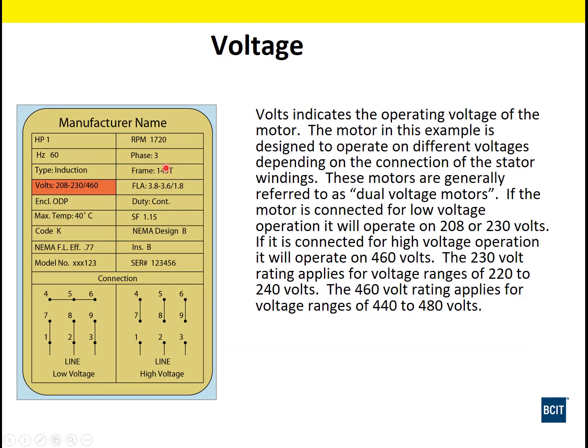Now we look at voltage. It's pretty straightforward, I hope. That's the maximum voltage we can apply to the motor. A lot of these motors are dual voltage, so that means we can have a low and a high voltage setting for them. And some of the lower voltage you see here is going to have a little bit of a range, so you can run them at 208 to 230 volts.